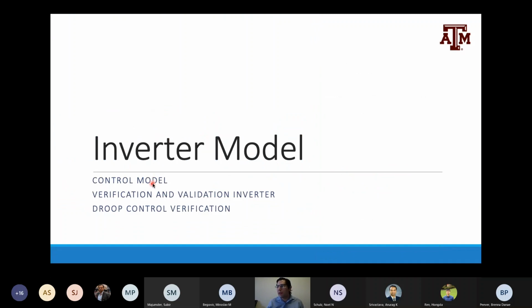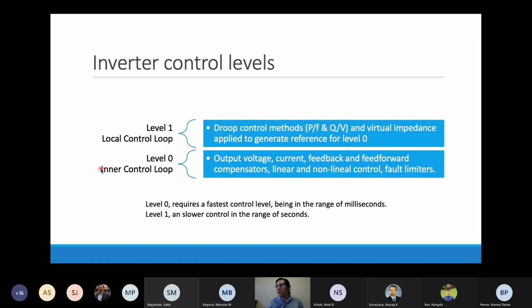Regarding the inverter model, I will talk a little bit about the control and some validation we did, including the validation of the droop method that is implemented in this one. As Professor Begovic mentioned before, we have two levels. Level 1, which is the local control loop, and level 0, which is the inner control loop. The most important part is to know that level 0 requires a faster control, which should be in the range of milliseconds. And level 1 is a slower type of control, which should be in the range of a few seconds. Here are all the blocks, the control levels that the equipment has. I will show in the next slide a little bit more detail about this.